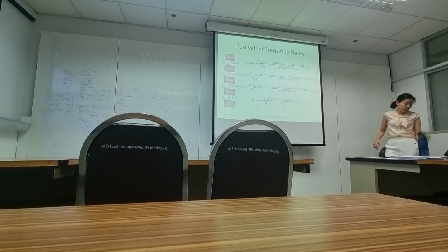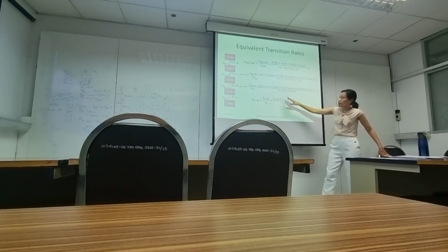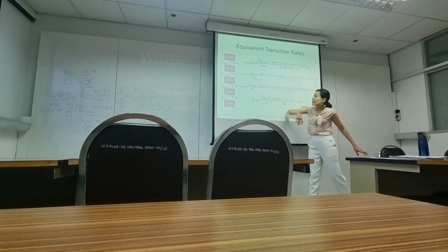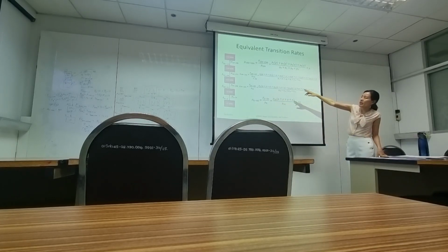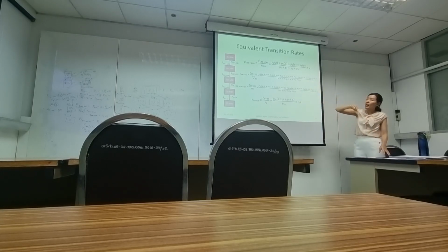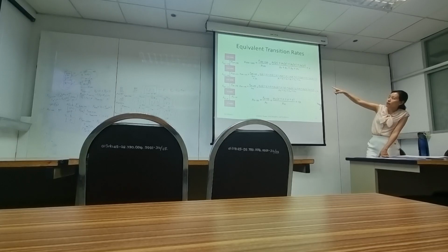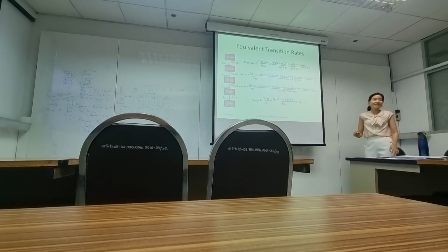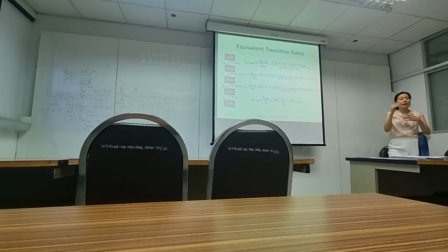And here, you have 3 from 50 to 100. And then from 100 to 150, you have 2 mu. And from 150 to 200, you have 1. Okay, so it's almost like a pattern. And that kind of pattern is what they would use for the uniformization algorithm.